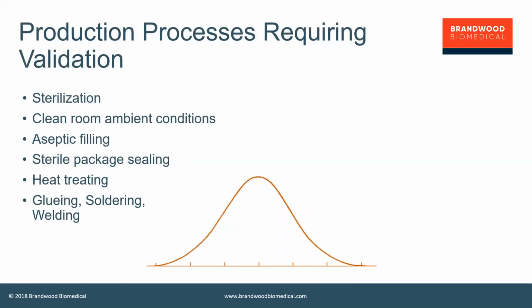So these are what is known as special processes, which require validation by means of things like doing a production run of a defined series of devices and then taking a statistical sample from those, or testing the whole lot, doing a 100% sample from a test run, from a validation run, to see that if you control the conditions in a defined way, you get an understood and defined output which pre-validates the production. There are very well tested ways of doing that with things like sterilization, where you can do known cycles and half cycles on product and measure the sterility in a statistical way.